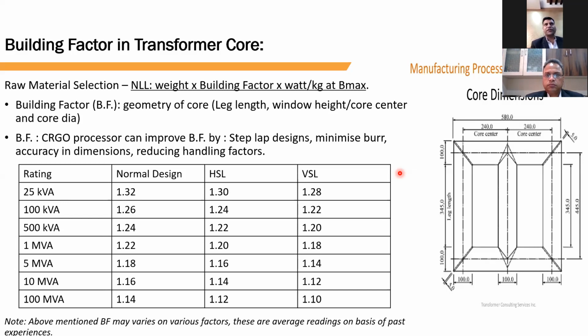So we reduce such handling processes and move toward automation, avoiding direct contact with the CRGO. Also, at the stacking stage, machines are available worldwide that do core assembly with robots—lifting cut laminations and stacking them directly on the stacking table, making full cores using robots and conveyor belts. Such technology is developed where people optimize this building factor.